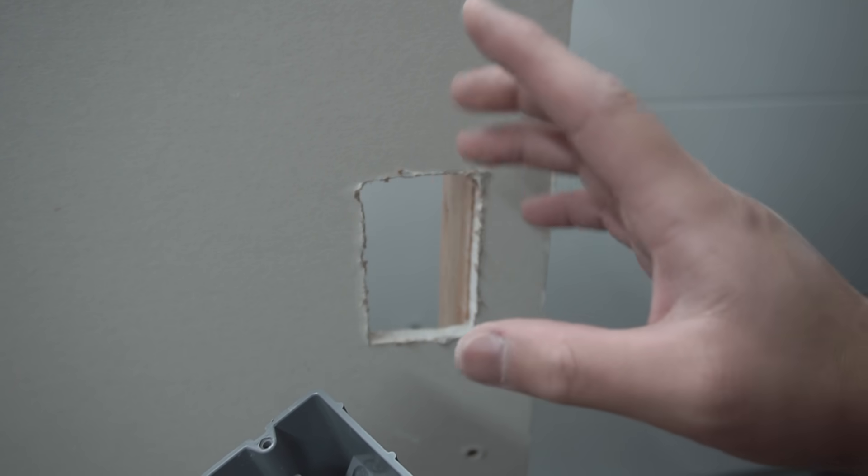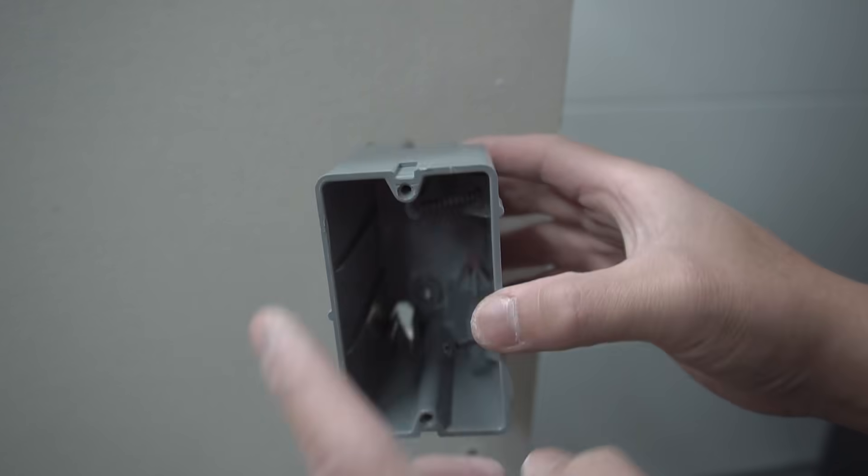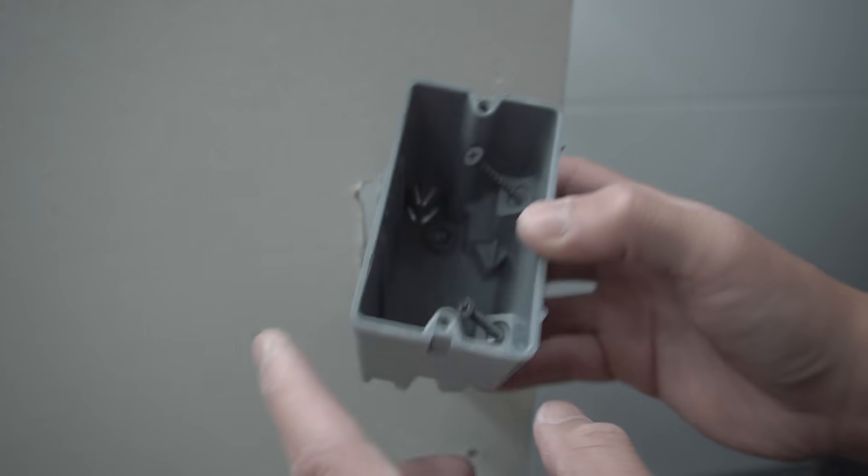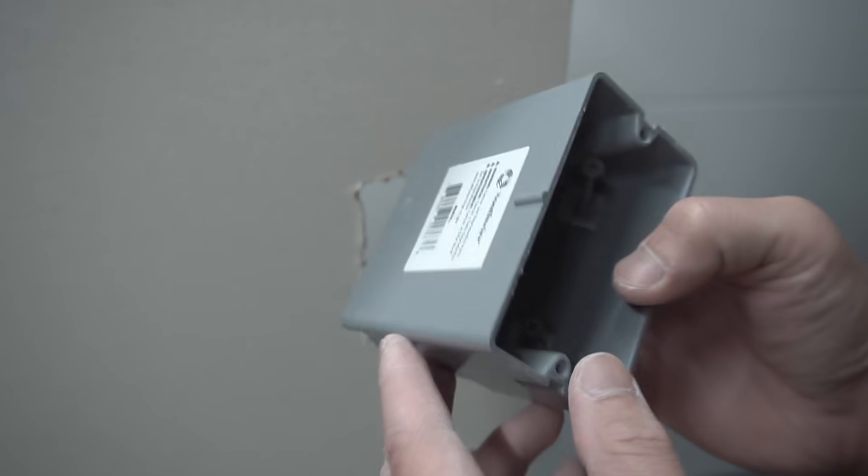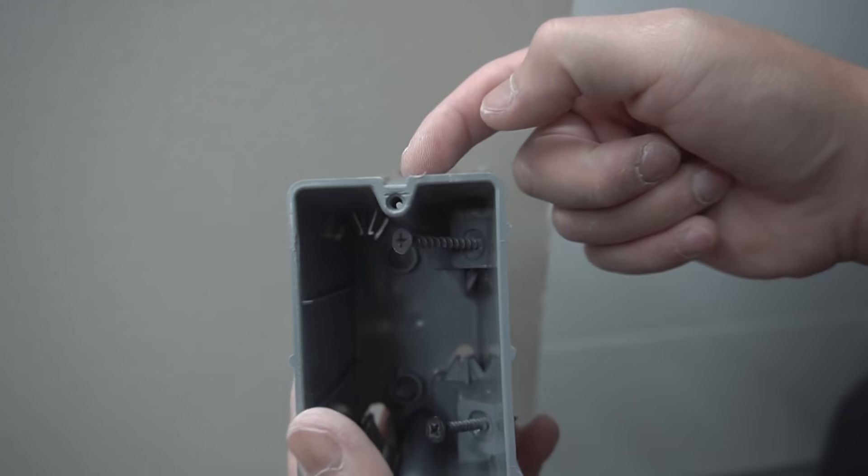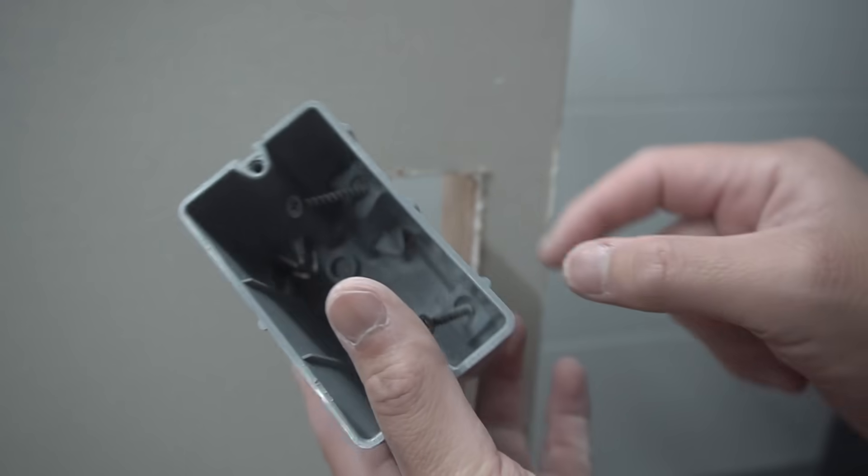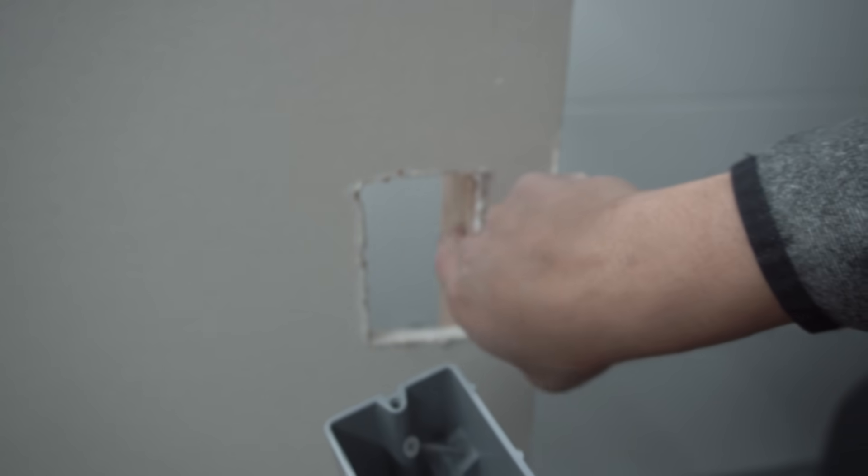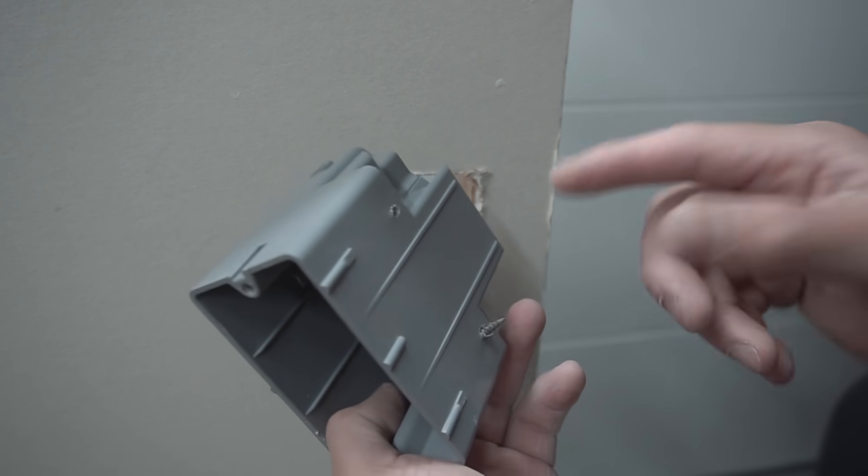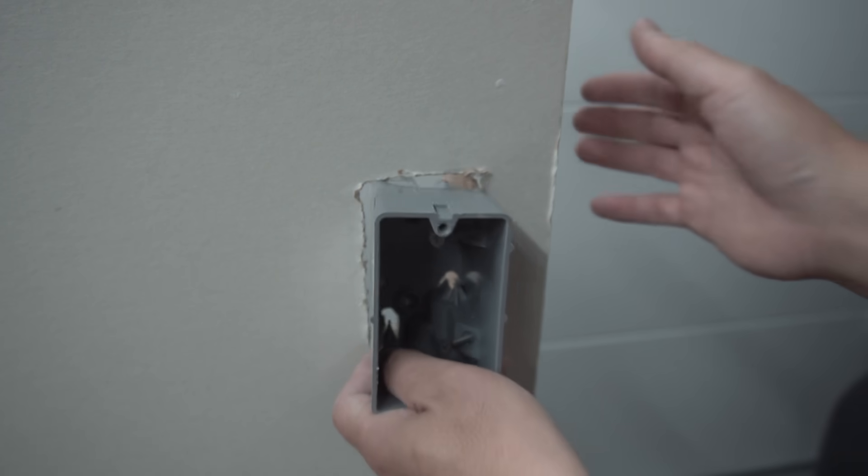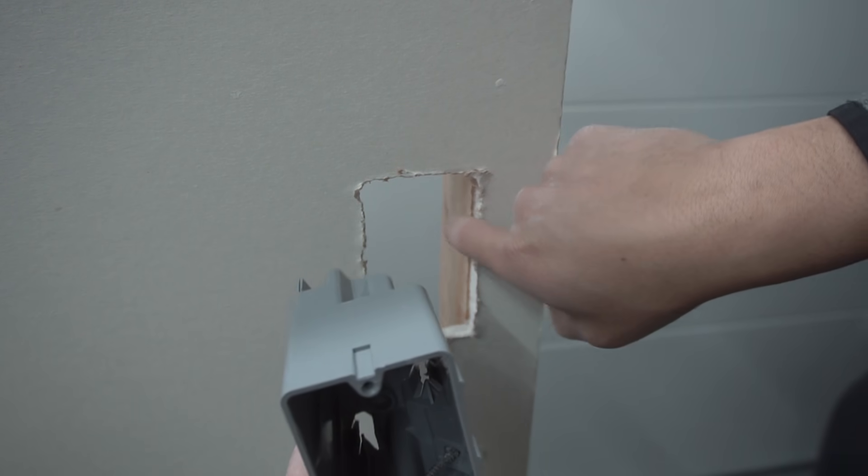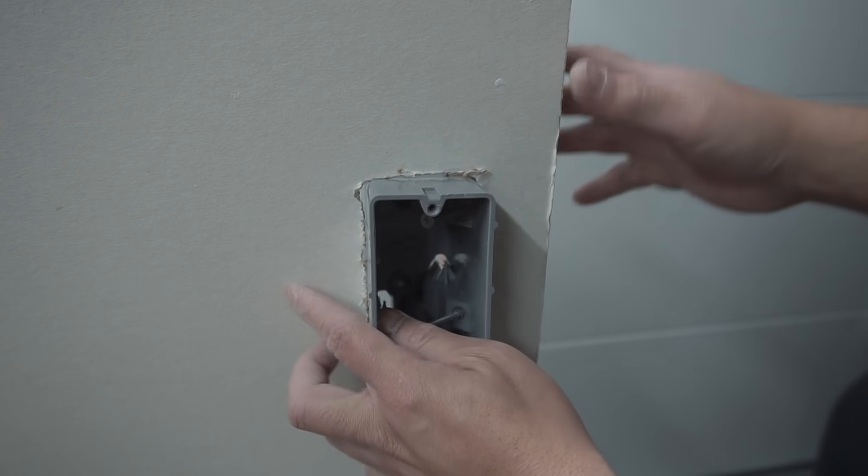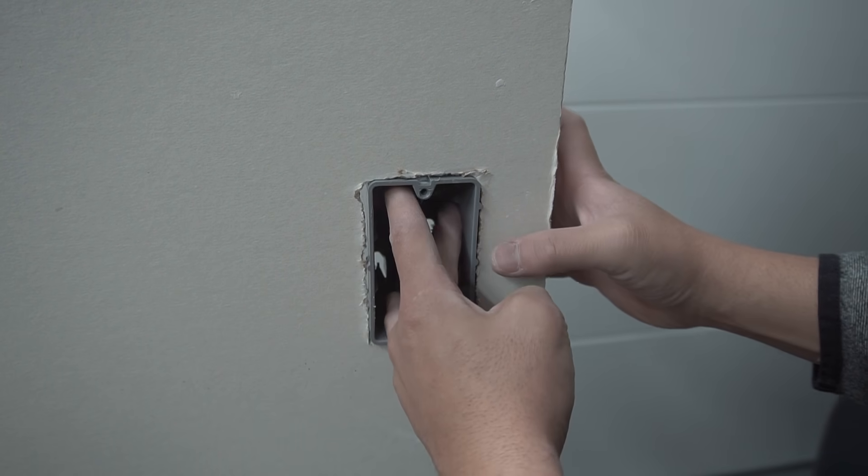Now the one that I highly suggest that you use is this adjustable type Old Work J-Box. Now it's pretty much the same as the other one. But instead of it having those two clips at the bottom, this one just straight screws onto the stud itself. And I believe in my opinion, it's a lot stronger. It makes contact directly to the stud. And all you have to do is screw this in.